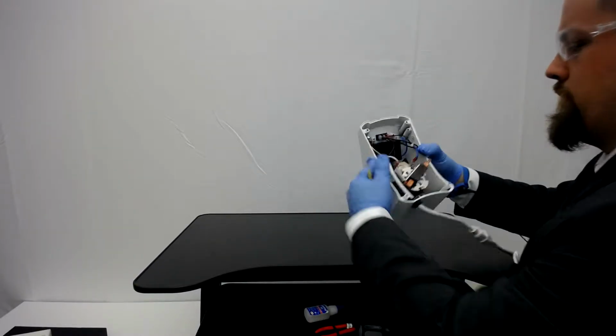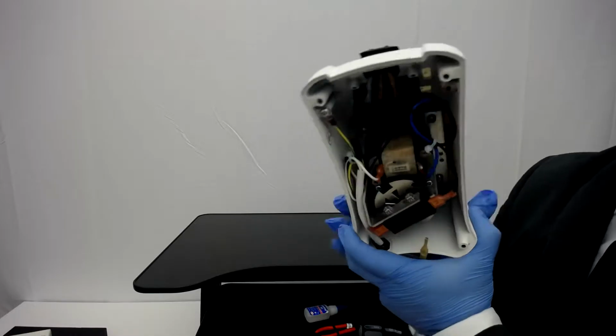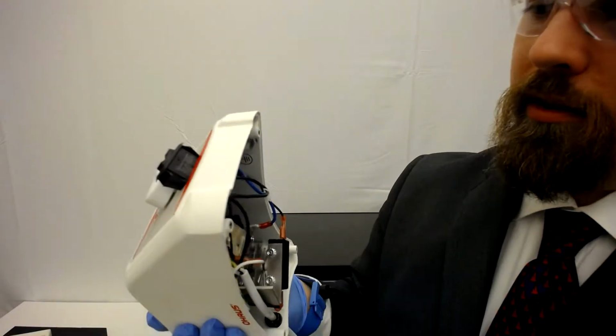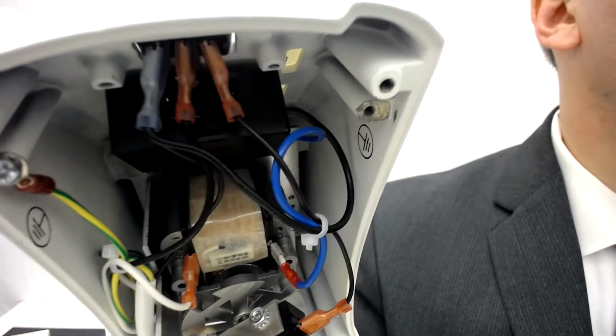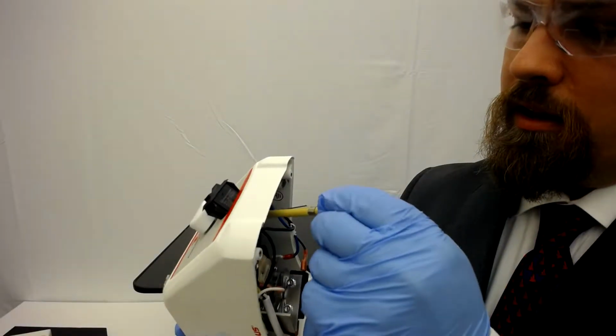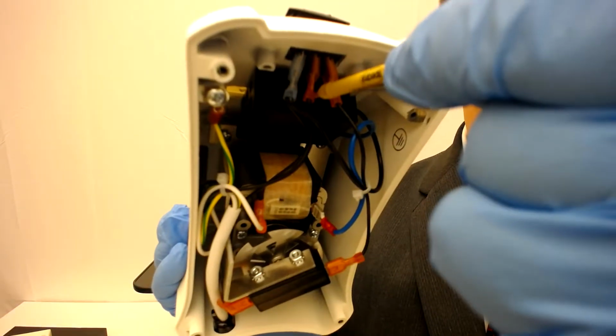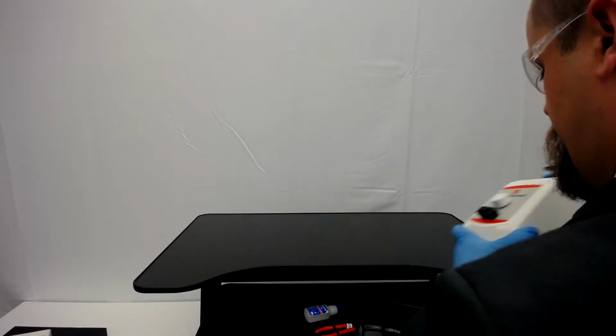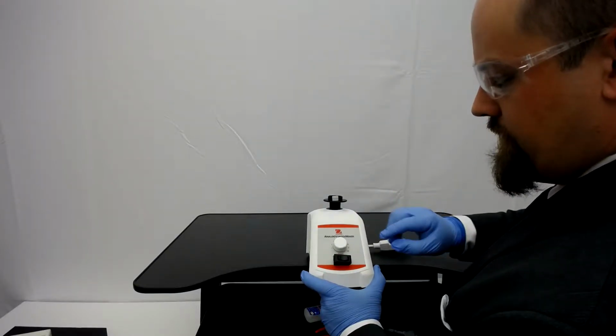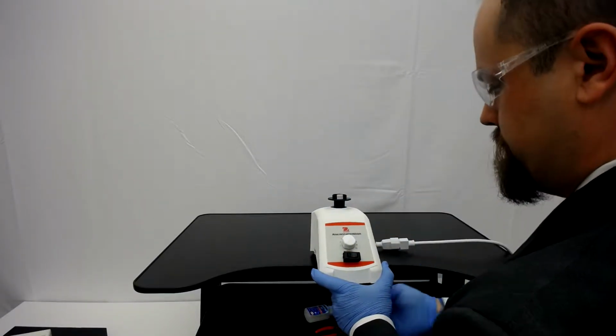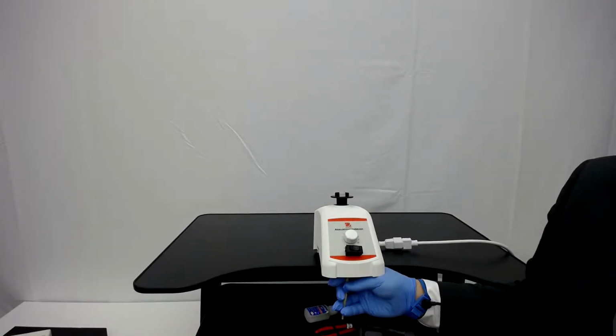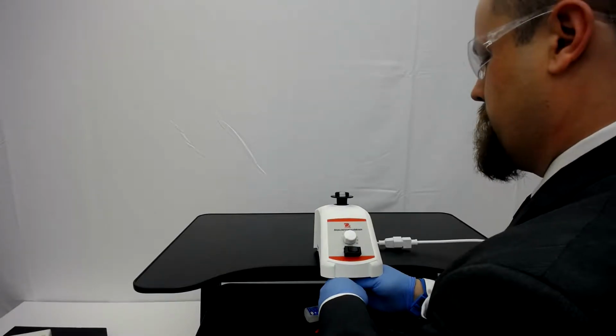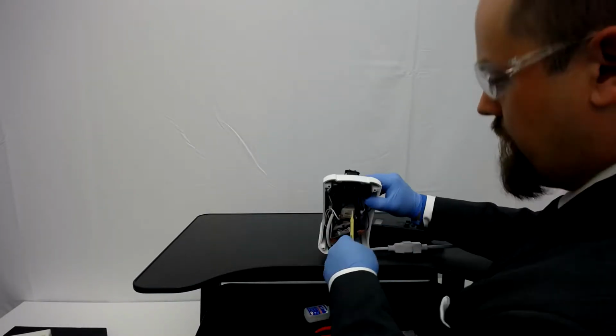Next, we're going to go right into the trim pot. And I don't know whether you'll be able to see it on this one. You saw it on the hot plate stirrer. But we'll go in between these two fast-on connectors and place the flat of the trim pot tool into the slot in the rheostat. We're going to turn it down to 1. And we're going to calibrate it to 500 RPM, plus or minus 150 RPM, again, using the phototachometer.